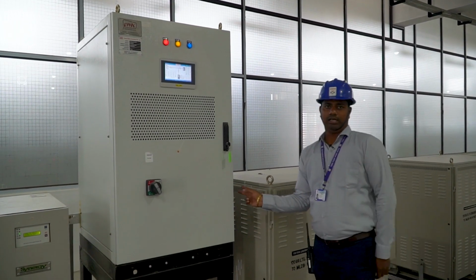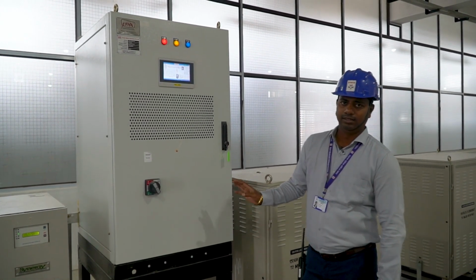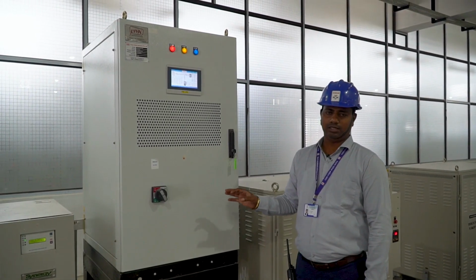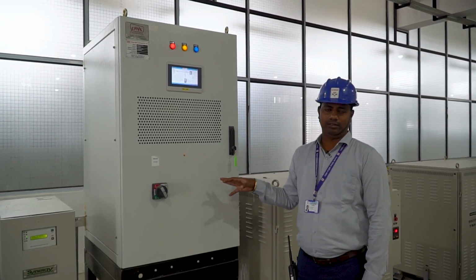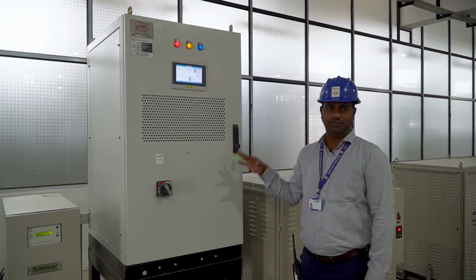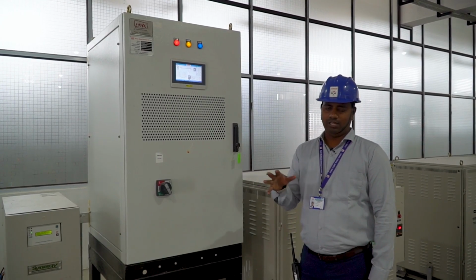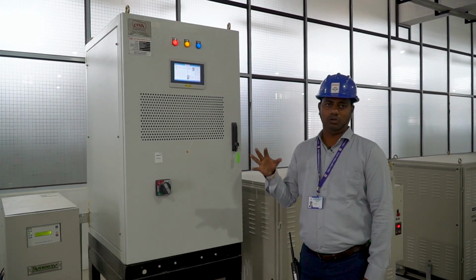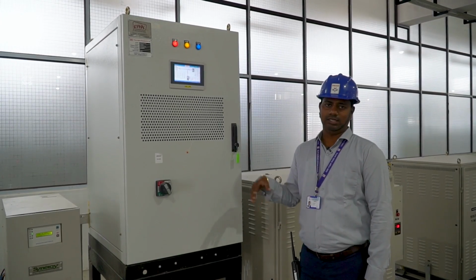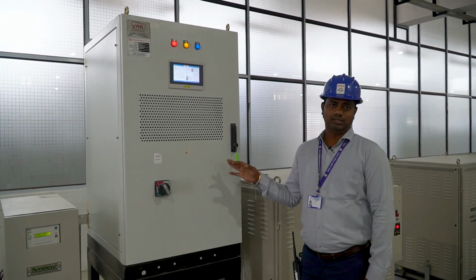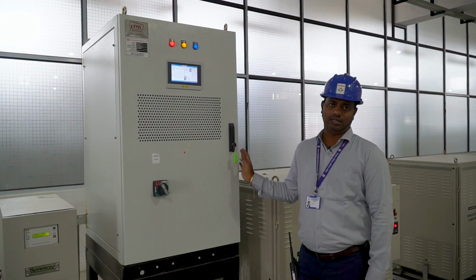So we have a dedicated harmonic filter setup here. The purpose of this harmonic filter is to filter the harmonics generated in the VFD drives. So we have VFD drives for TT gantry loading pumps. Whatever harmonics are generated in the VFD drive have to be suppressed. This panel takes care of that work.